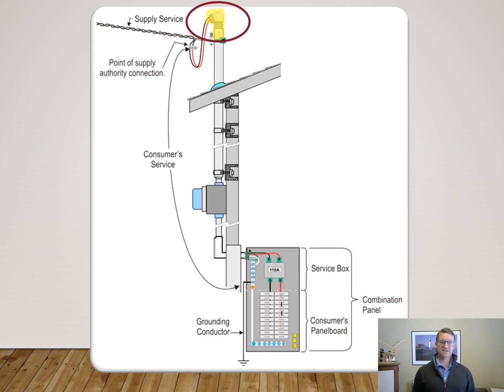The service head is a device used on overhead services to protect the service raceway and the service equipment from any penetrating water due to weather. The point of attachment is the location where the supply service and the consumer service meet and are connected together, and on an overhead service, it's usually the same place where it's connected to the building.